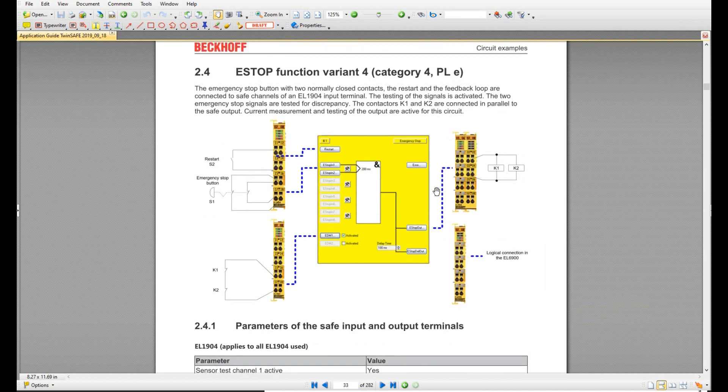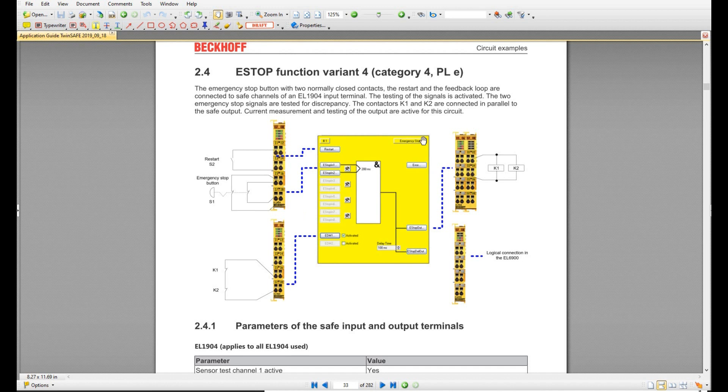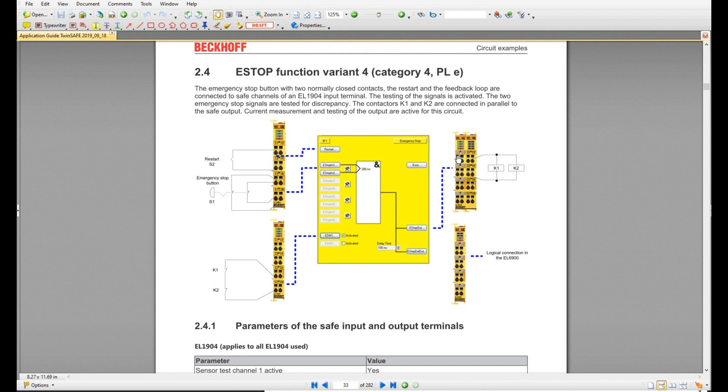If we go to here, to implement this E-stop control loop, it combines a safety module, safety circuit, safety programming function block, and the safety relay. It's quite clear to show all the loops: how to design the wiring, how to use the module, how to wire the module, which safety function block you need to use, and for the safety relay, how we can wire the safety relay and how we can use the EDM monitoring loop. So it's quite clear.